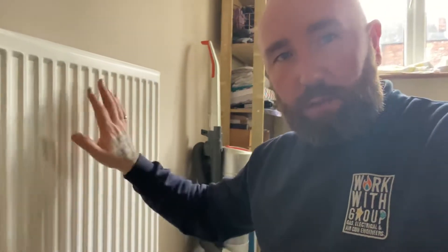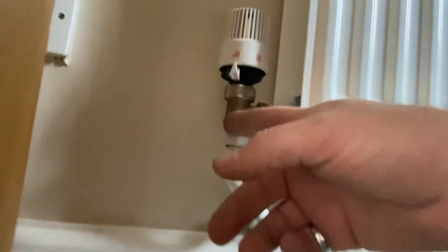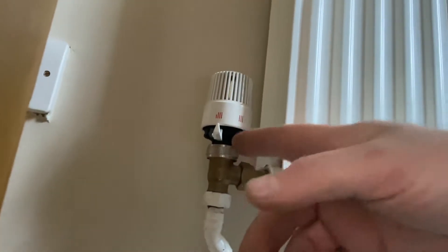Hi folks, from Work With Group here, a little how-to video on when you've got a cold radiator. We've used our thermal imaging camera and we could see that down at the valves we had heat, but nothing on the panel itself. So what we have is this chap here called a thermostatic radiator valve.